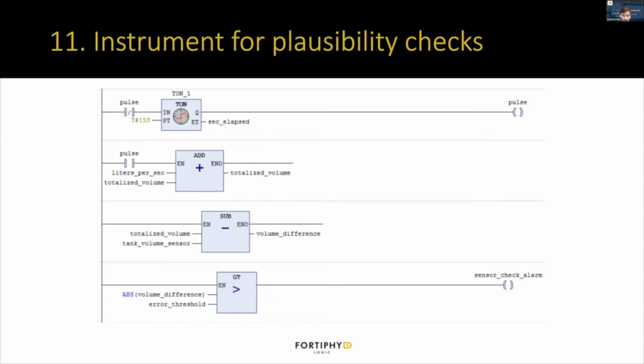So an example in CODESYS, I've implemented here just a pulse that happens every 1 second, and we're using that pulse to add up how much flow is currently going through this flow sensor. So when we see that pulse, we add the current liters per second into some totalized volume variable. We then compare the difference between the totalized volume and what the tank volume sensor is telling us. And if the absolute value of that difference is ever over some threshold, then we say, hey, there's a major discrepancy here between what the tank sensor is saying and what has gone through our flow sensor. So maybe one of the sensors is failing or wrong, or maybe an attacker is injecting false data into the system.